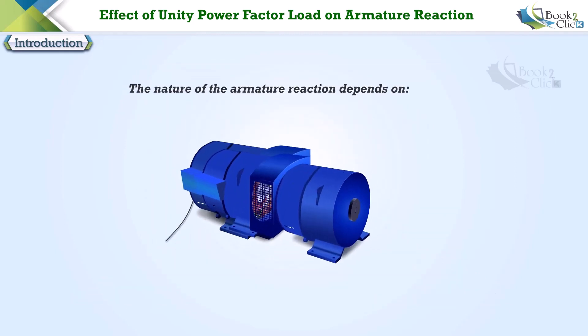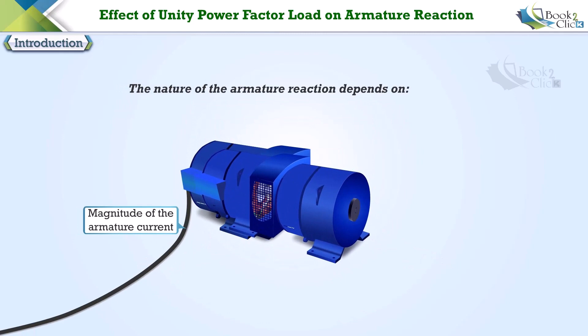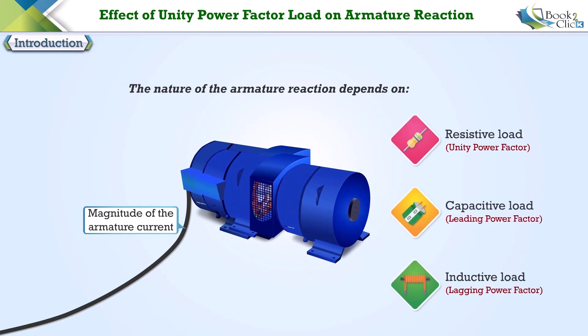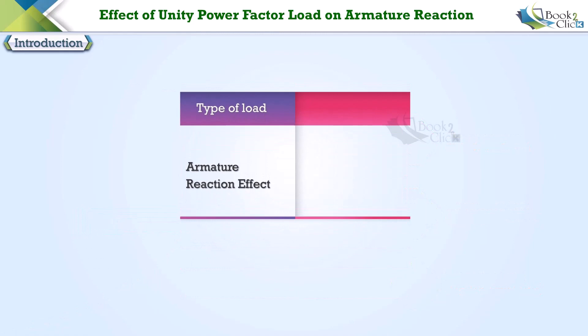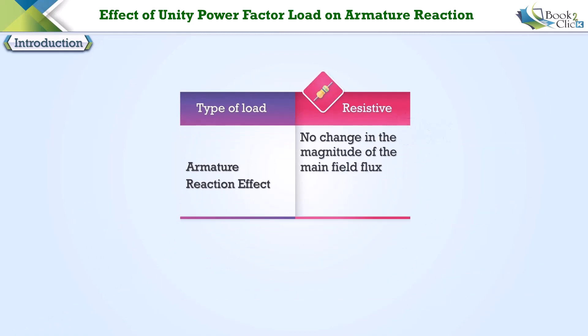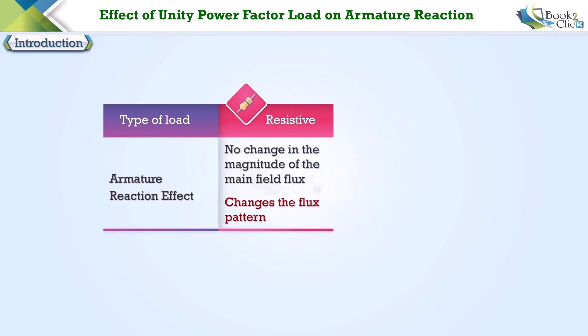The nature of the armature reaction depends on the magnitude of the armature current and the type of load connected to the alternator. If the load connected to the alternator is resistive, the armature reaction will not change the magnitude of the main field flux, but it will change the flux pattern.